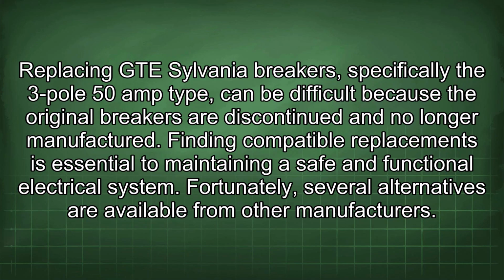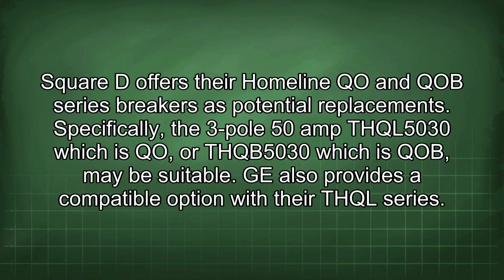Replacing GTE Sylvania breakers, specifically the 3-pole 50 amp type, can be difficult because the original breakers are discontinued and no longer manufactured. Finding compatible replacements is essential to maintaining a safe and functional electrical system. Fortunately, several alternatives are available from other manufacturers. Square D offers their Homeline QO and QOB series breakers as potential replacements. Specifically, the 3-pole 50 amp THQL5030, which is QO, or THQB5030, which is QOB, may be suitable.